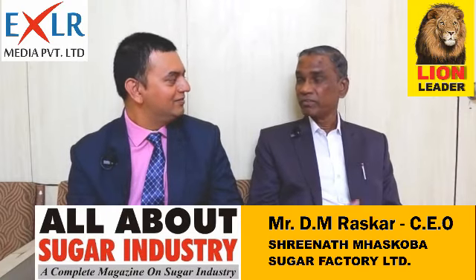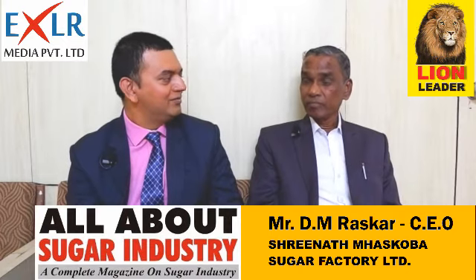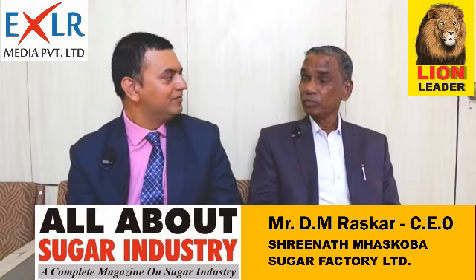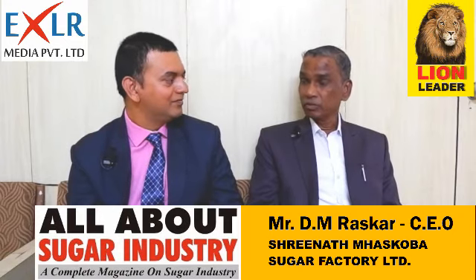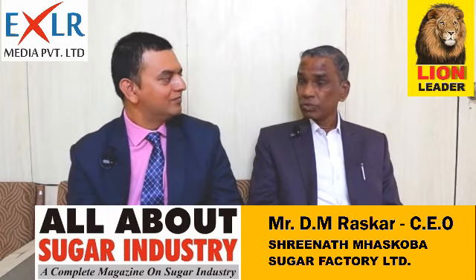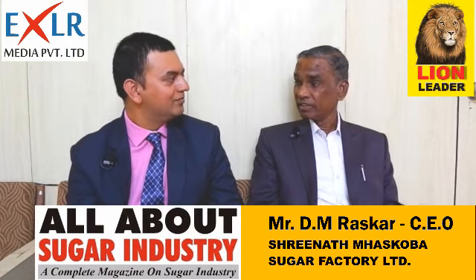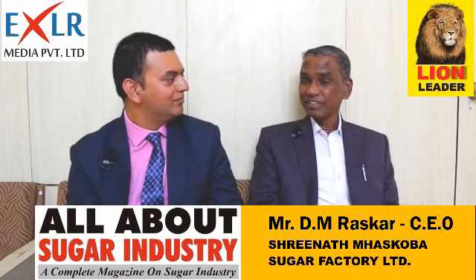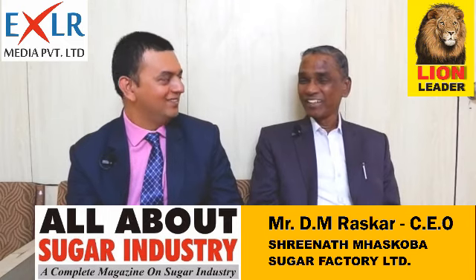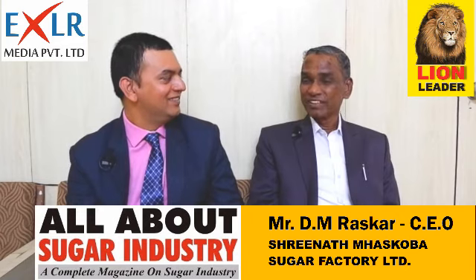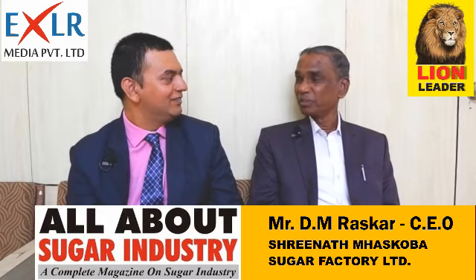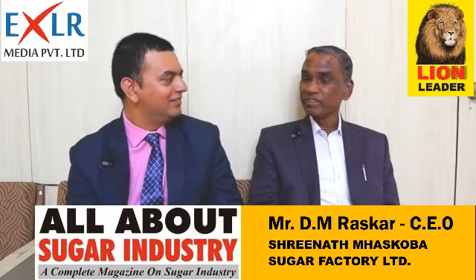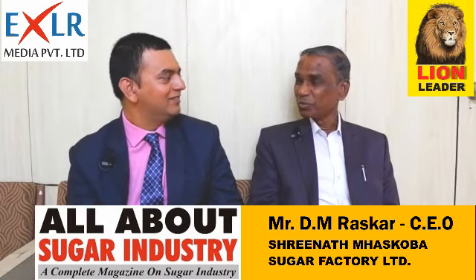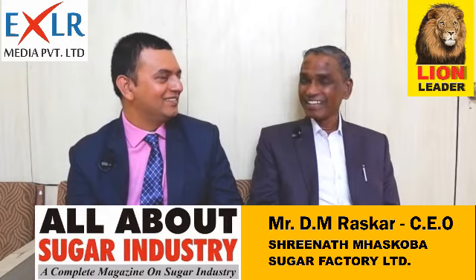Then we decided to purchase a 10 megawatt capacity turbine, and we prepared one project for 10 megawatt power generation. So excluding the boiler, we need not purchase it, because that was already with us, accidentally. Otherwise we would have had to purchase a 25 or 30 tons per hour boiler, but that was not available in the market. So whatever was available, that 70 TPH boiler, we dared to purchase and start here.